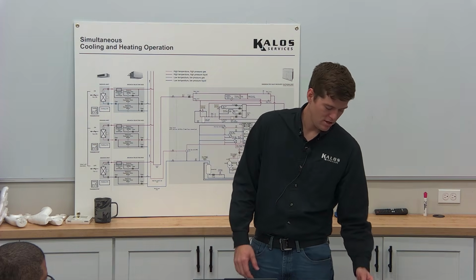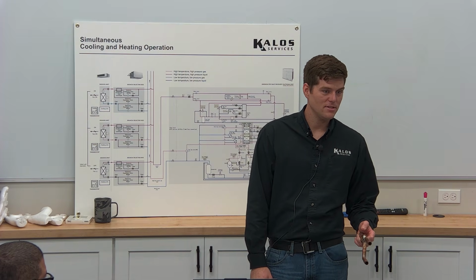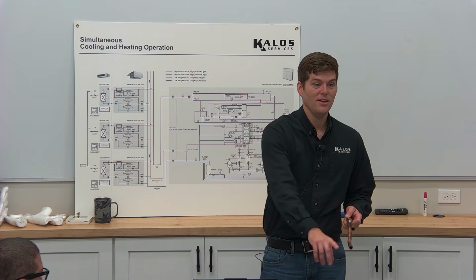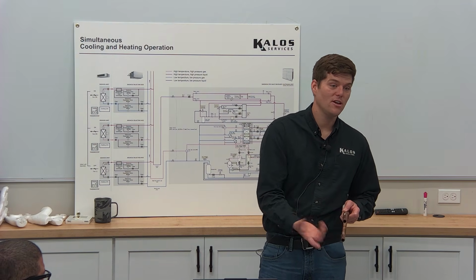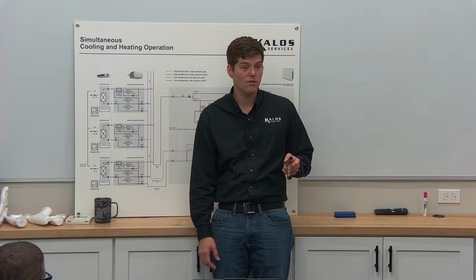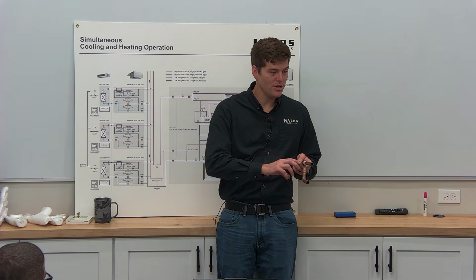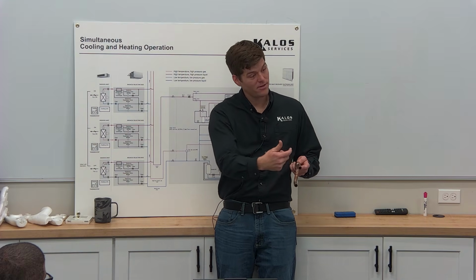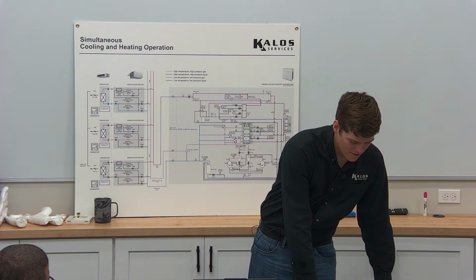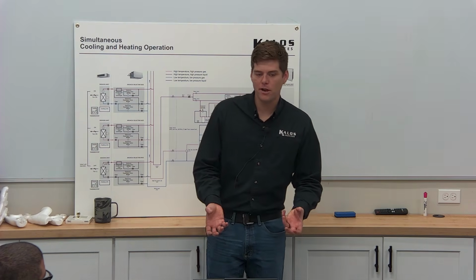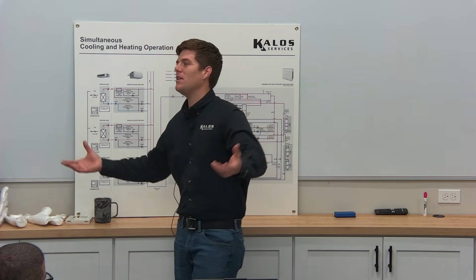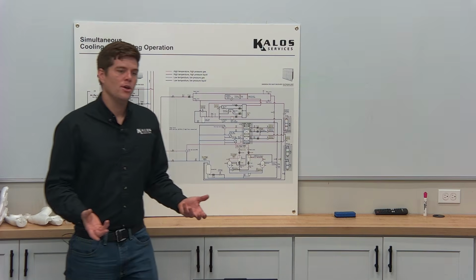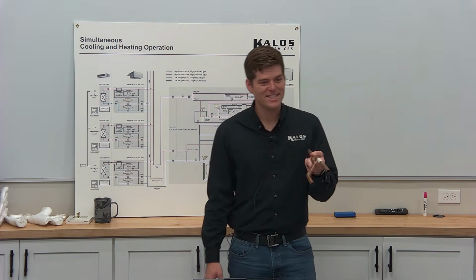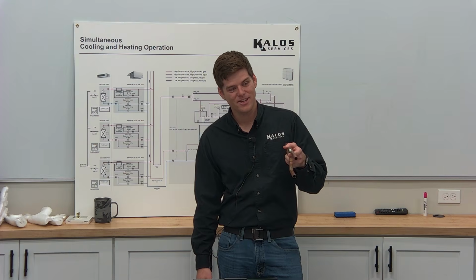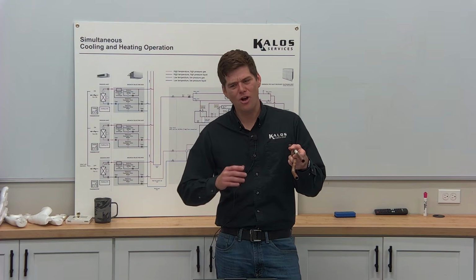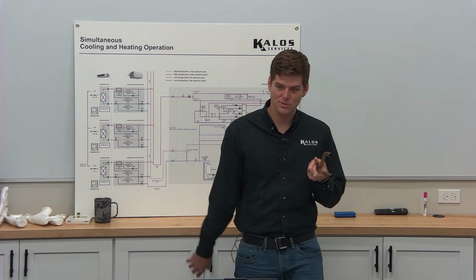But when you see installations like this, what happens is, right? All the liquid goes to the bottom. What happens? You start to pull oil. So let's say this is on a closet that has no heat load or cooling load at all, and that unit barely ever turns on. During normal operation, when you've got refrigerant flowing back, right, you're going to get oil that's going to trap in that line. Everything is intentional. That's the premise behind VRF, right? So yes, we have all these indoor units. We have all this flexibility. We can do all these things with VRF. But something so simple as this to this can kill compressors, can cripple a system, can deliver awful capacity to the fan coil that's connected to this one, if I put it like this.